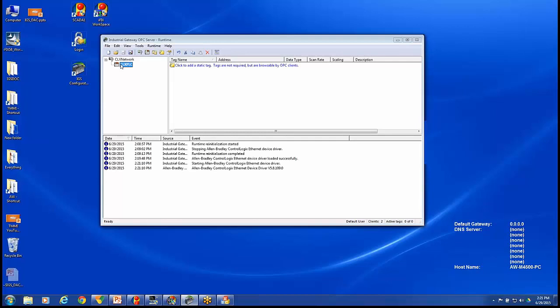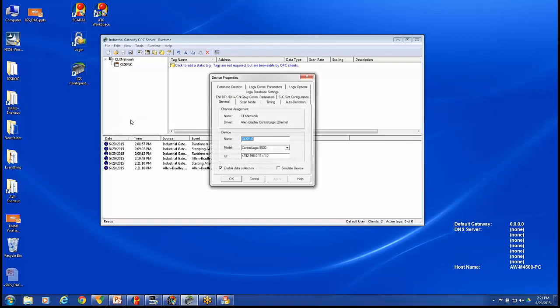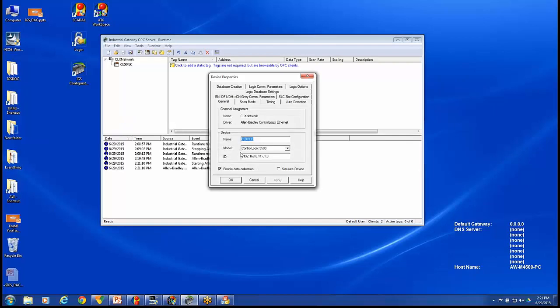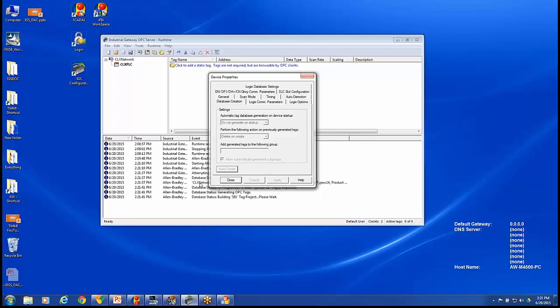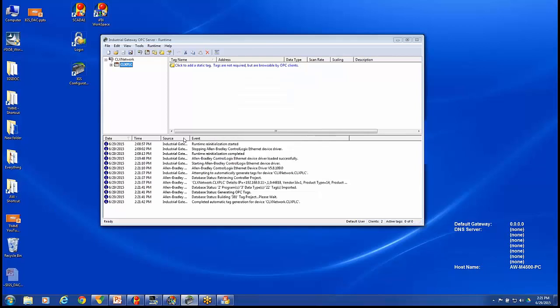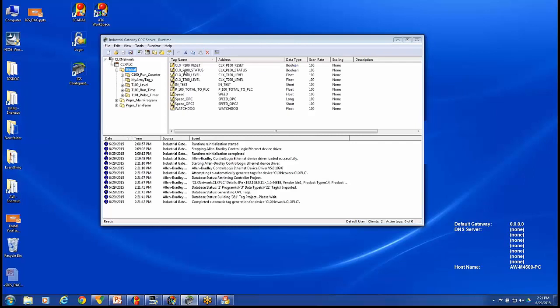We want to populate this with information from the PLC. So we're going to right-click and go to Properties. Here I can redo the settings that were done when we were hitting all the Next buttons. But I'm going to go to Database Creation. And I'm going to tell it to auto-create. It's actually communicating with that PLC and pulling back the tag names and programs in that PLC. I can see that it's completed, so we'll hit Close. And I'll expand this out. These are the tags that have been built inside of my ControlLogix PLC and programs that are in there also.